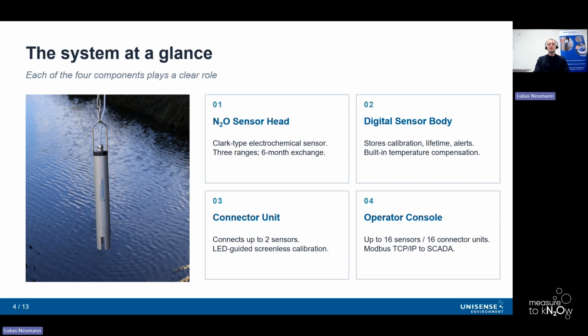And this is where the LED-based calibration procedure takes place. And then, of course, we have the operator console, the brain of the operation, which can take up to 16 sensors, 16 connector units, all in series, and will connect straight to your SCADA using Modbus TCP IP and other options as well, of course. A key point to highlight here is the modularity of the system. So you can really start small with 2 sensors, 1 connector unit, 1 console, and then scale up without needing to change the architecture and as needed on your site.